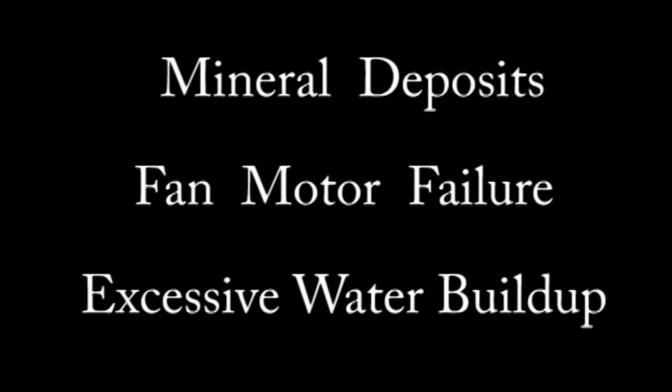What kind of damage? The most persistent problem you will encounter will be calcium or iron buildup on fragile cooling fins. Also, on a low-pressure system, there will be excessive water discharge, as well as 100% humidity saturating your fan motor.